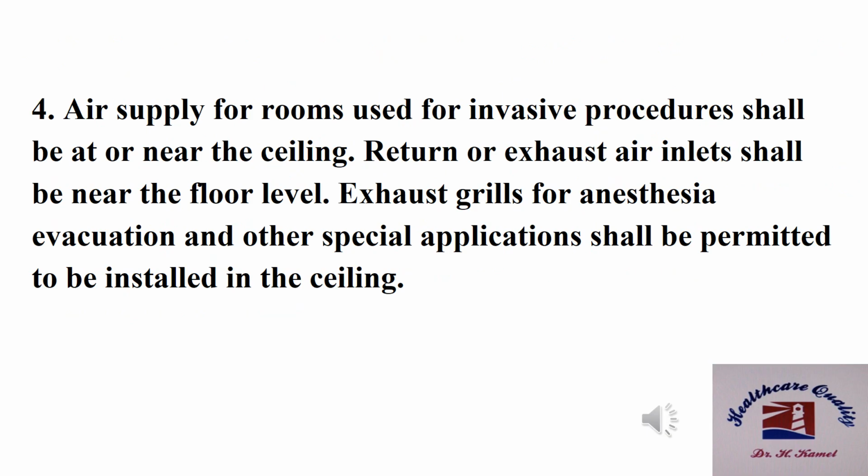Air supply for rooms used for invasive procedures shall be at or near the ceiling. Return or exhaust air inlets shall be near the floor level. Exhaust grills for anesthesia evacuation and other special applications shall be permitted to be installed in the ceiling.